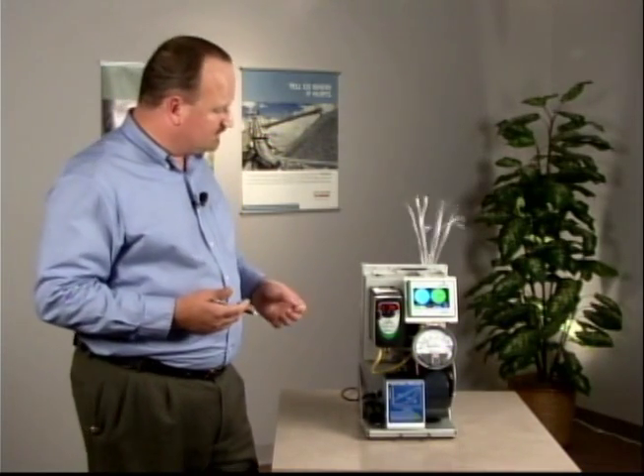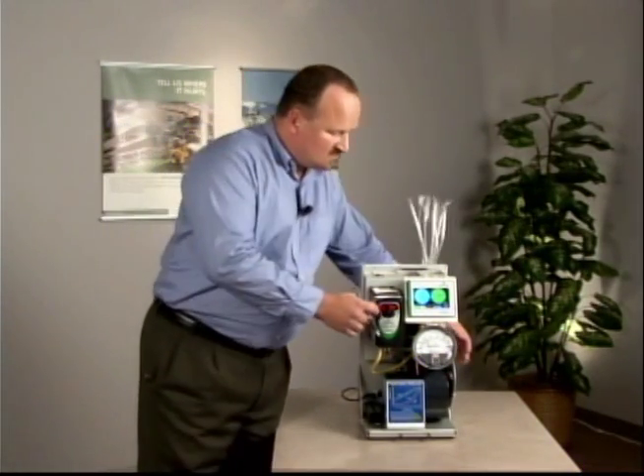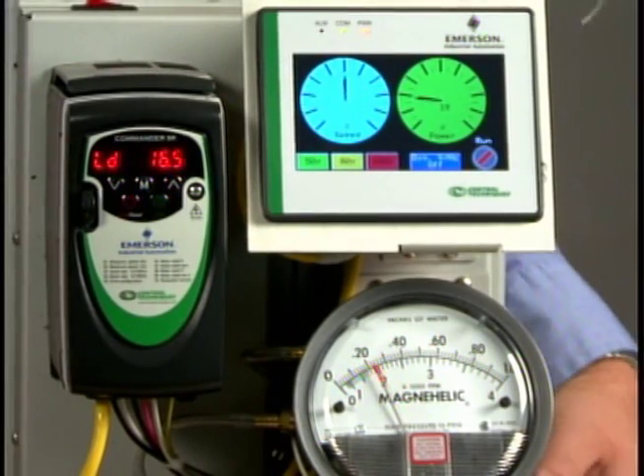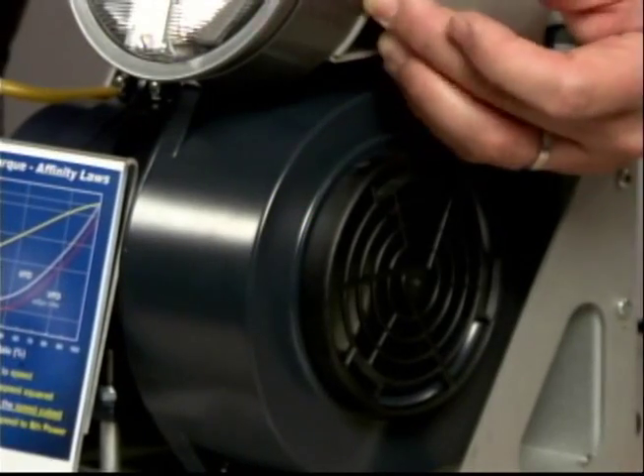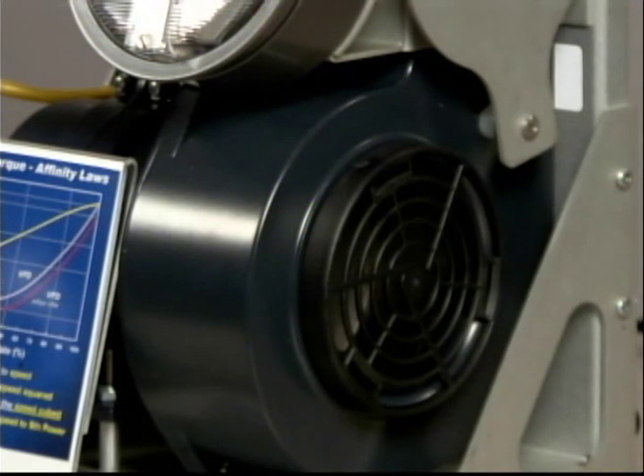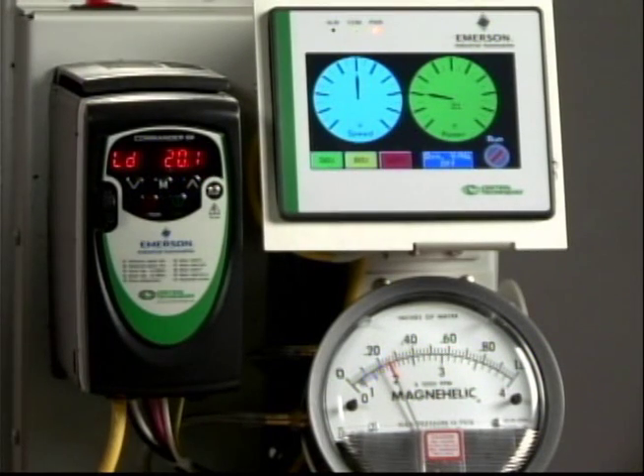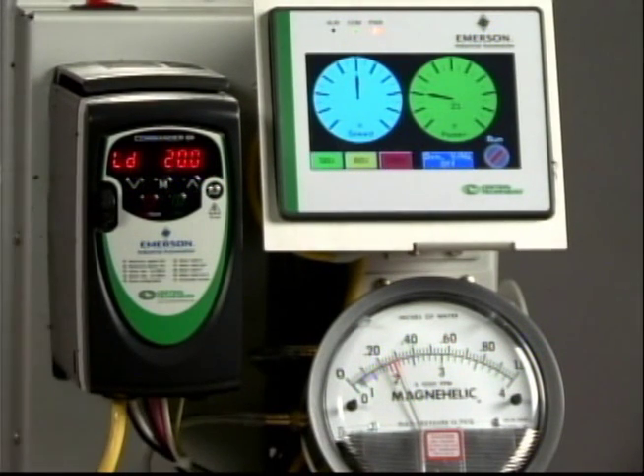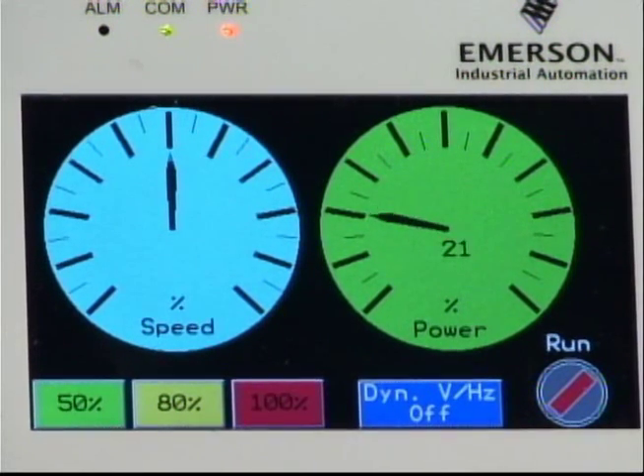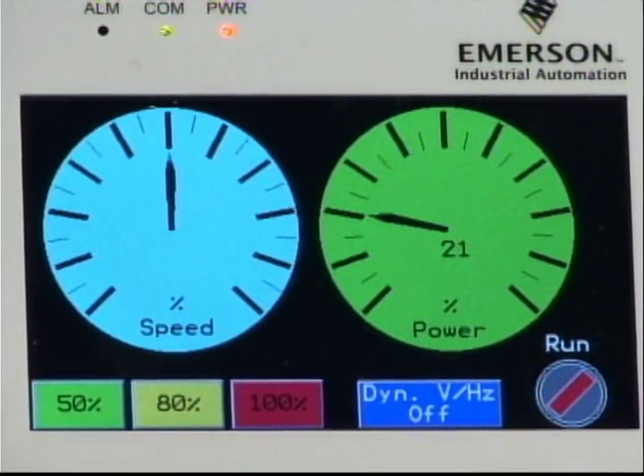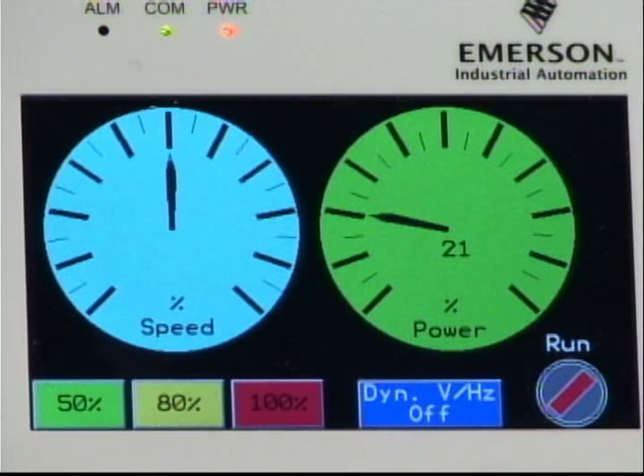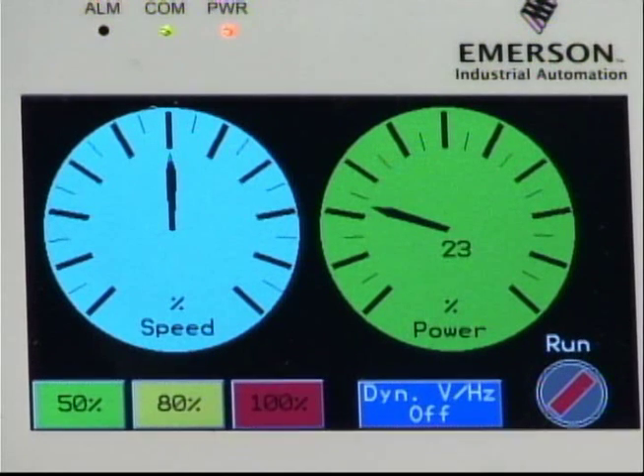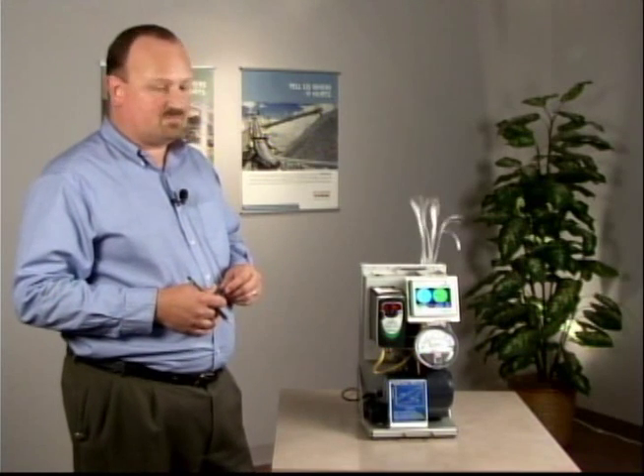Now an alternative to this method is to change the speed of the motor and remove the mechanical flow control device. If we contrast this operating mode, we find still at about 2,000 CFM of air, the energy has dropped to around 22%. This fan speed is at 50%. That really illustrates the control method and the benefit of direct control of the motor speed.